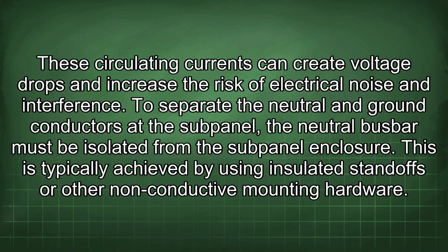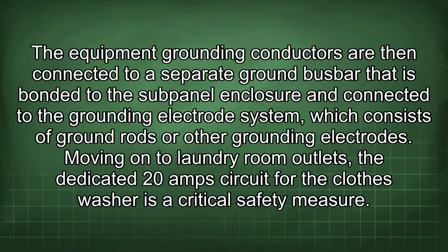To separate the neutral and ground conductors at the subpanel, the neutral busbar must be isolated from the subpanel enclosure. This is typically achieved by using insulated standoffs or other non-conductive mounting hardware. The equipment grounding conductors are then connected to a separate ground busbar that is bonded to the subpanel enclosure and connected to the grounding electrode system, which consists of ground rods or other grounding electrodes.